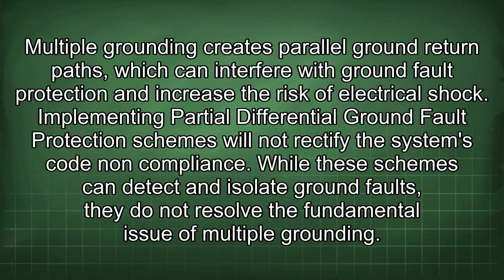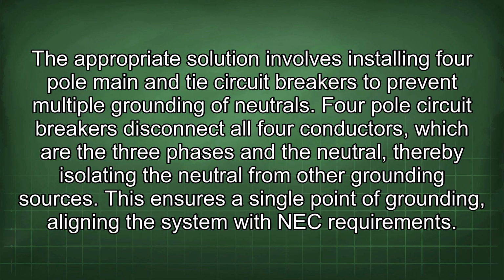Implementing partial differential ground fault protection schemes will not rectify the system's code non-compliance. While these schemes can detect and isolate ground faults, they do not resolve the fundamental issue of multiple grounding. The appropriate solution involves installing 4-pole main and tie circuit breakers to prevent multiple grounding of neutrals. 4-pole circuit breakers disconnect all 4 conductors, which are the 3 phases and the neutral, thereby isolating the neutral from other grounding sources. This ensures a single point of grounding, aligning the system with NEC requirements.